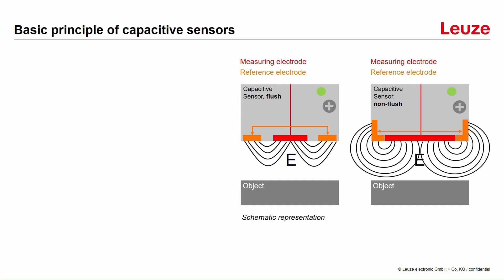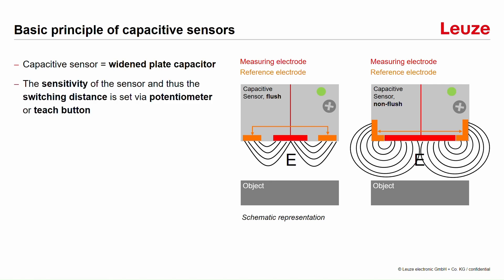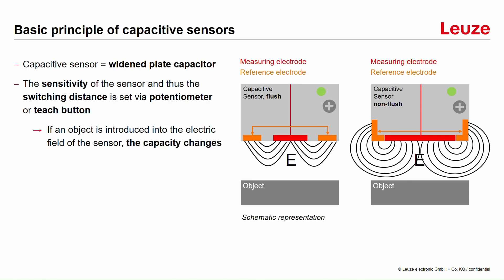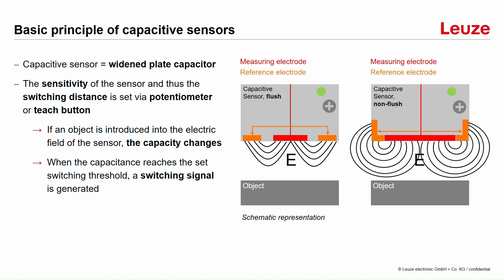What does this mean for a capacitive sensor? In the two pictures here, you can see on the left side a flush sensor, where the electric field and the active zone are only on the front. On the right picture, you see a non-flush sensor, where the electric field is not only on the front but also on the sides. A capacitive sensor can be understood as a widened plate capacitor. We can also adjust the sensitivity of the sensor, for example with a potentiometer. If we bring an object into the electric field of the sensor, the capacity will change. And if the capacity reaches the level we have already adjusted, there will be a switching signal — that is the basic principle of a capacitive sensor.